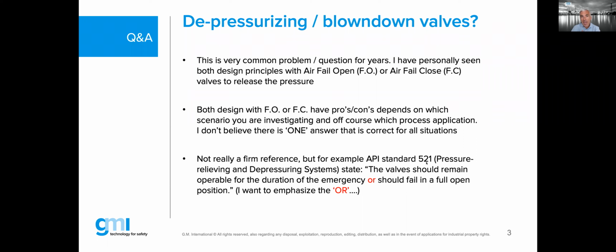For those who don't know the API 521 standard, that's a specific application note describing pressure relieving and depressuring systems. And I make a statement, and I actually copied the statement here in my slide. They said the valve should remain operable for the duration of the emergency or should fail in a full open position. And I'm really trying to emphasize here the "or" statement, because if you think about it, the valve should remain working for the duration of the emergency situation.